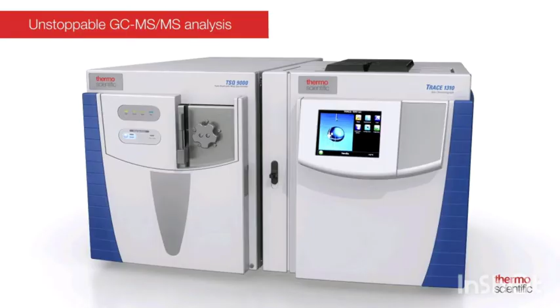Triple quadrupole mass spectrometry. The triple quadrupole mass spectrometer is a tandem mass spectrometer in which the first and third quadrupoles act as mass filters and the second acts as a collision cell to fragment the selected precursor ions and generate fragment ions. The TQMS is probably the most famous and widely used tandem MS, which is relatively simple and easy to use with good reproducibility to offer various applications at a low cost.